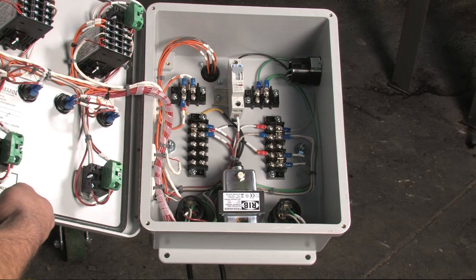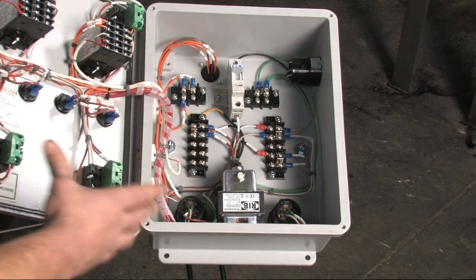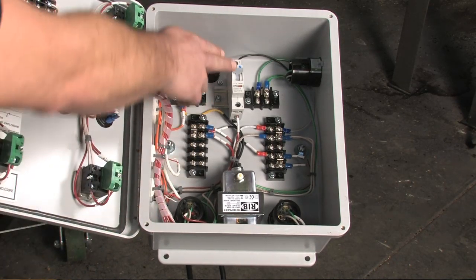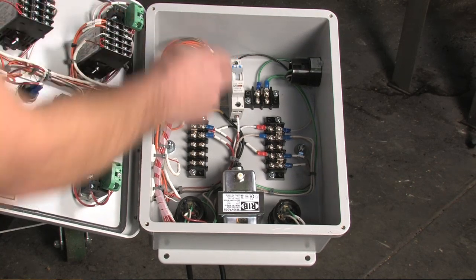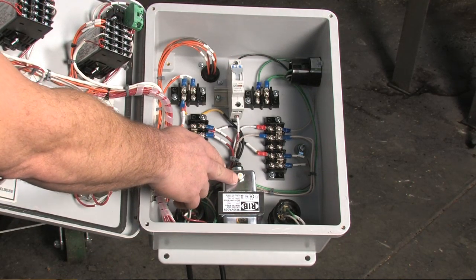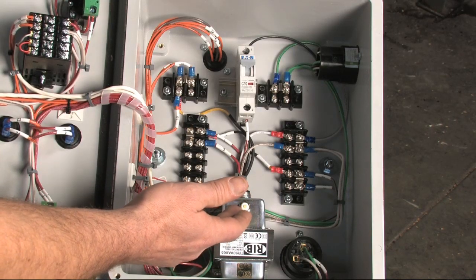open the panel. Inside the panel, you'll see the back of the controllers, the switches. You have a main breaker here, and you also have a resettable breaker on the transformer. If for some reason this control transformer breaker should trip, the button will pop up just about that far. It's hard to tell, but what you do is you push it down, it would snap, power would come back on to the ignition modules. The most common fault for that is getting the low voltage circuit wet. If you spill something from a tank, washing it down, typically with power on, is what would cause that.